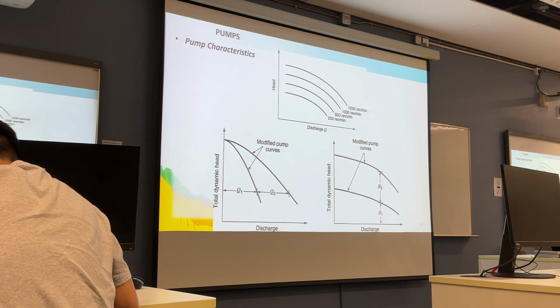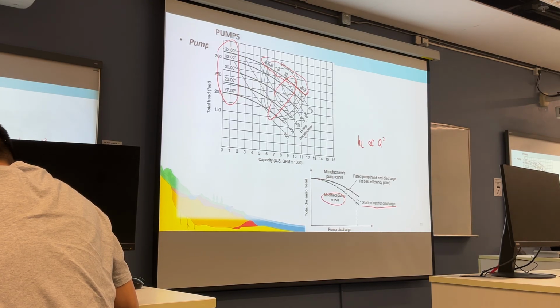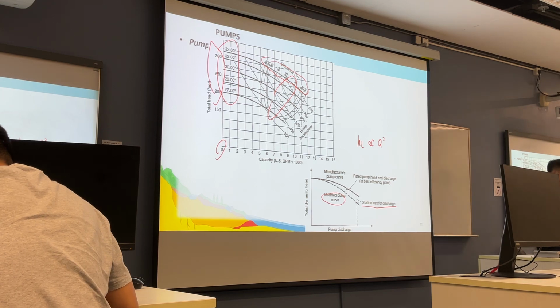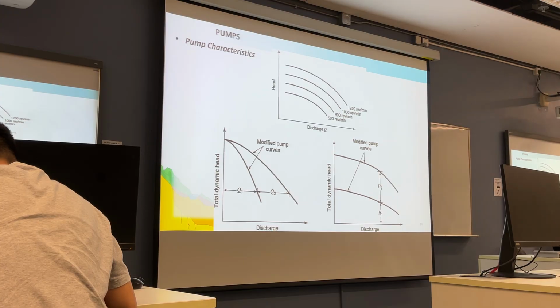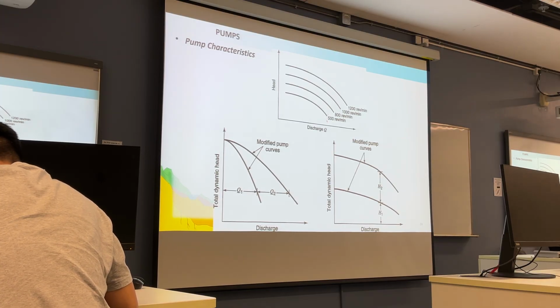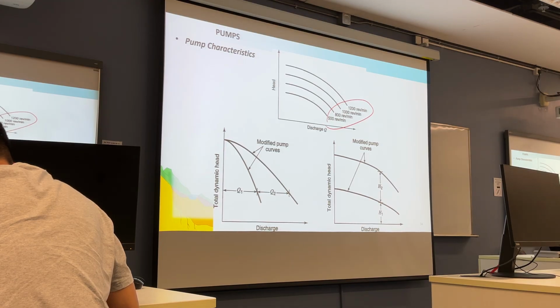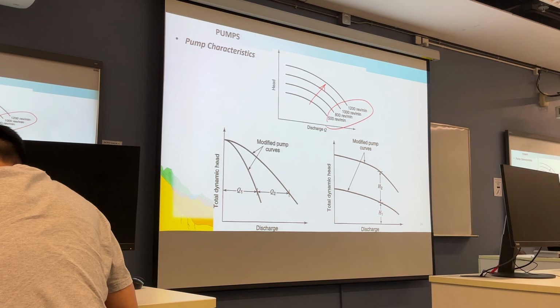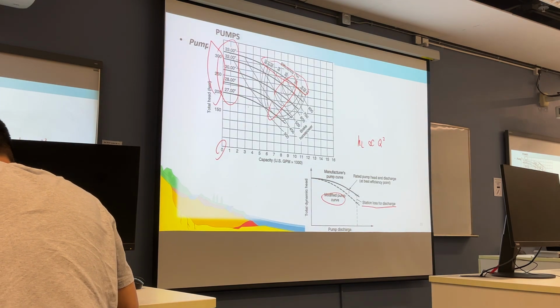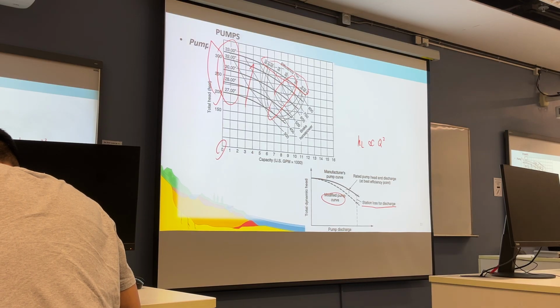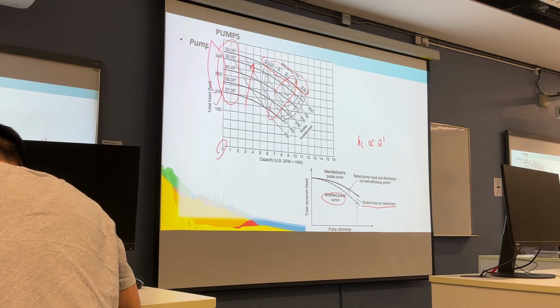Here the statement talks about this head being called the shut-off head, because this maximum head appears when it is at zero discharge. And at zero discharge, it means the maximum head actually appears. So this is called the shut-off head. Now the figure here shows the same pump diameter running at different rotational speeds, different RPM, revolutions per minute. With a higher revolution, the pump curve shifts up. This curve shows that for a motor running at the same speed, as the diameter increases, the performance shifts up as well.